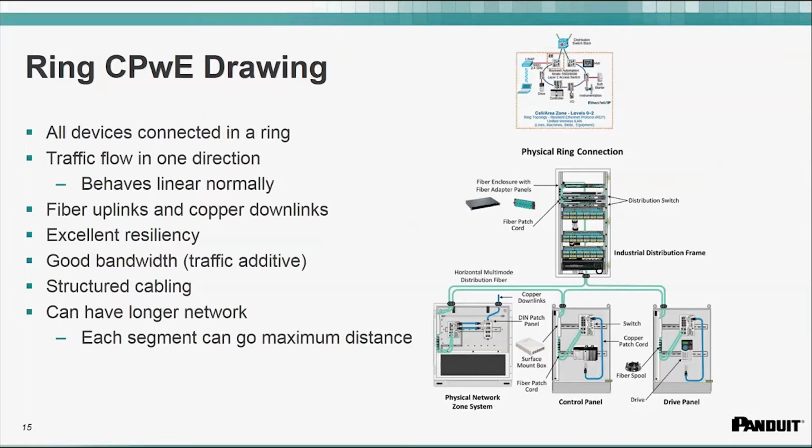This topology has excellent resiliency as it can survive one break in the connection, provided the path is totally independent and not in the same cable. If all links are in the same cable, the cable can be a single point of failure because a cut in the cable will sever all paths.